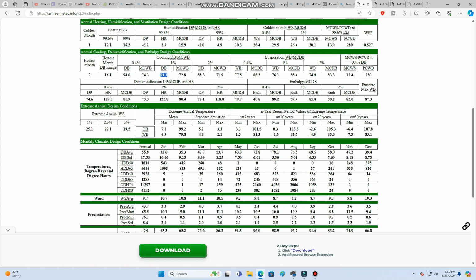So what this basically means, if you have a 98-degree day and you think there's a problem with your system because it won't drop below 80 degrees, you don't have a system that's doing anything wrong. You just have a system that wasn't designed to do that. And while that's certainly an inconvenience on the hottest days of the year, it's actually preferable to having an oversized system that brings a whole slew of problems the rest of the year. Now just keep in mind, none of this is really for actual diagnostic purposes. I'm just giving you guys the information you need to kind of determine whether something is right or wrong with your system and when it's time to take a closer look at things.